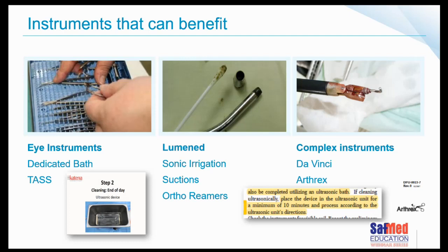For eye surgery, here's an example from the Katena guideline stating that at the very least, at the end of the day, devices should go into an ultrasonic cleaner. It makes good sense to have a dedicated bath for eyes so we avoid cross-contamination, and since eye instruments don't need a lumen flush, a smaller bath is ideal.